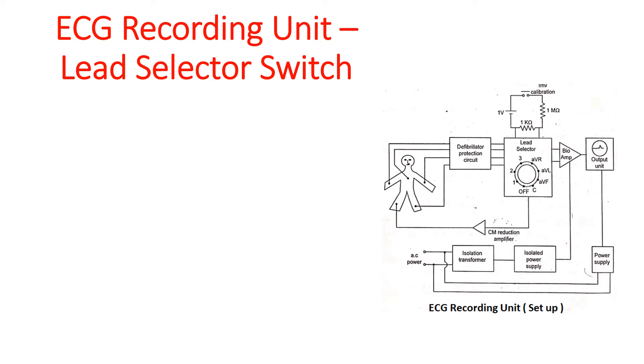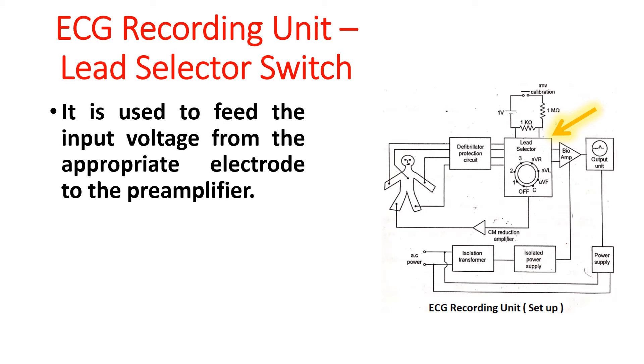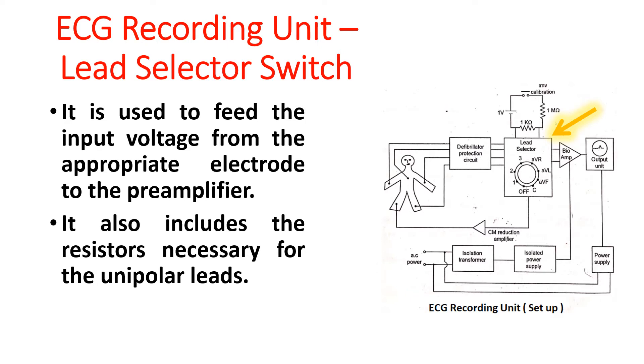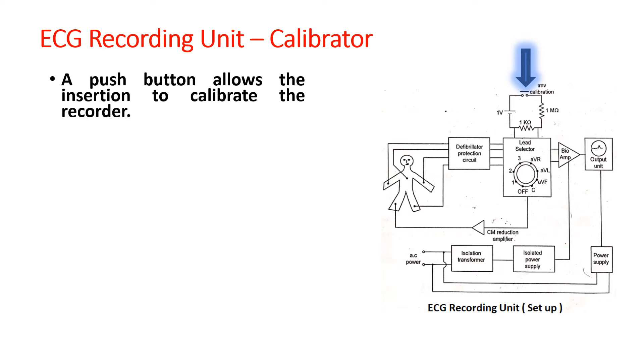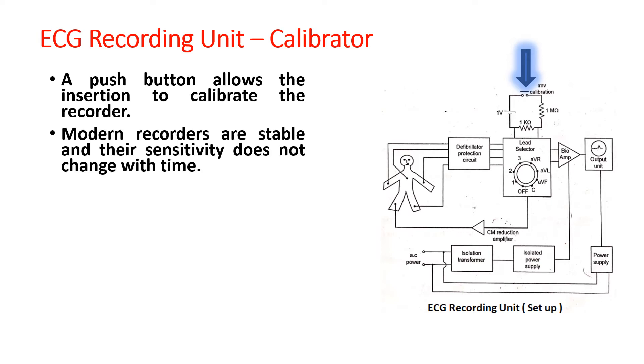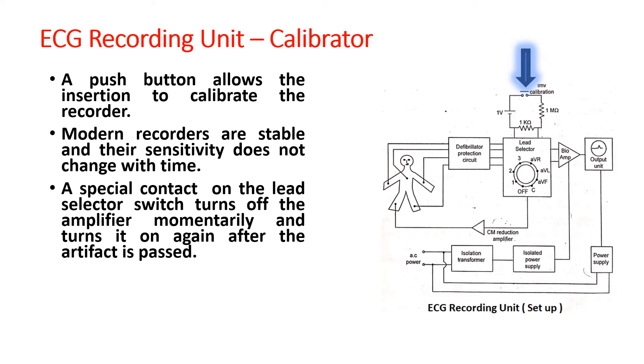Lead selector switch. It is used to feed the input voltage from the appropriate electrode to the preamplifier. It also includes the resistors necessary for the unipolar leads. The next block is the calibrator. A push button allows the insertion to calibrate the recorder. The modern recorders are stable and the sensitivity does not change with time. If it changes, the setting of the lead selector switch introduces an artifact on the recorded trace. A special contact on the lead selector switch turns off the amplifier momentarily and turns it on again after the artifact has passed.